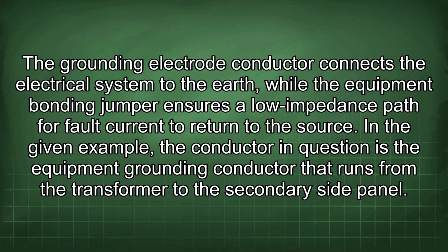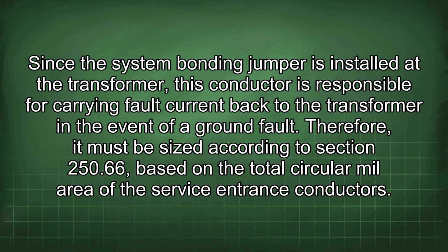In the given example, the conductor in question is the equipment grounding conductor that runs from the transformer to the secondary side panel. Since the system bonding jumper is installed at the transformer, this conductor is responsible for carrying fault current back to the transformer in the event of a ground fault. Therefore, it must be sized according to section 250.66, based on the total circular mil area of the service entrance conductors.